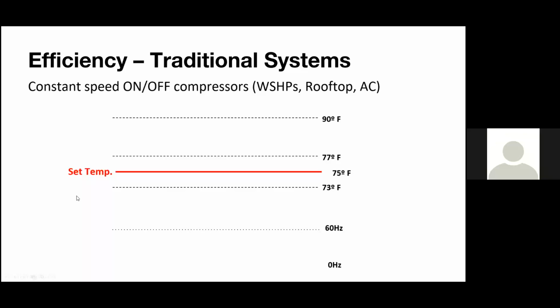If we're looking at this animation, our set point temperature is at 75 degrees. The compressor is going to turn on because we need cooling, and we're going to start at 90 degrees and bring that way down to 75 degrees, actually a little bit past 75 degrees. Now, looking at the compressor side, we're going to ramp up right away, a huge inrush of current, and then we're going to be at full bore around that 60 hertz in order to get that temperature to what we want. We want that 75 degrees to be comfortable, right?